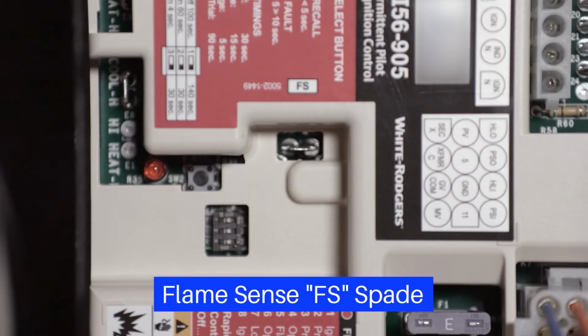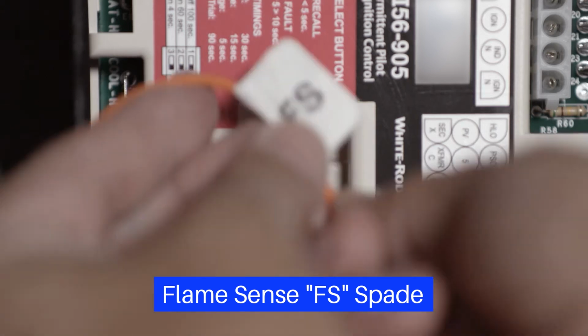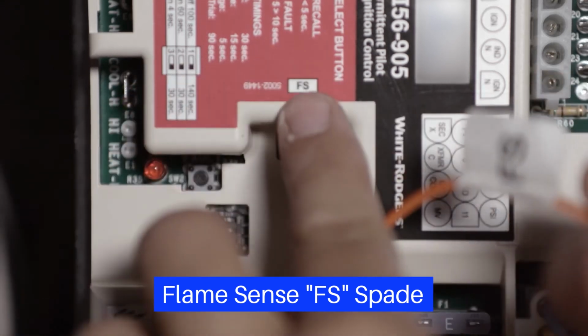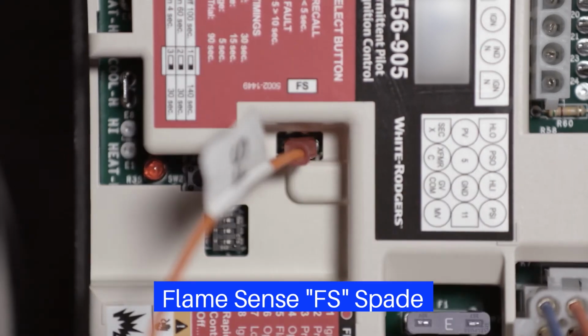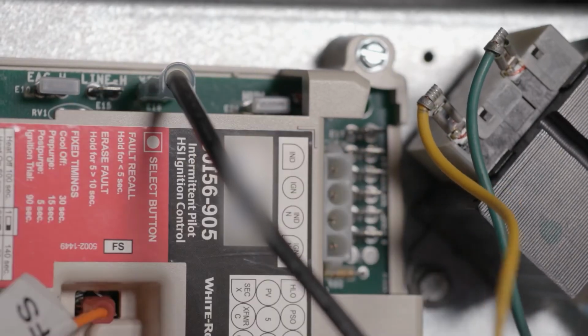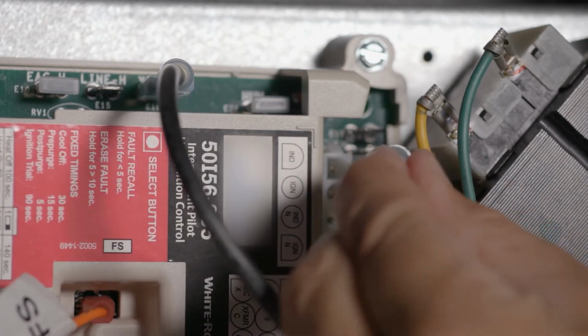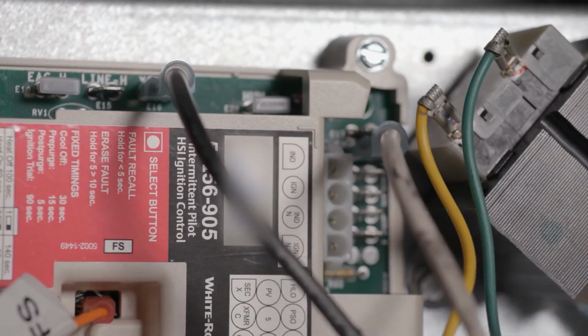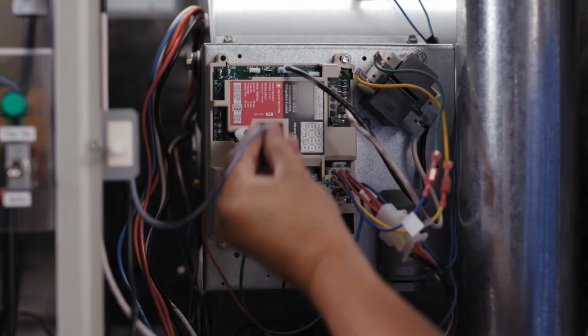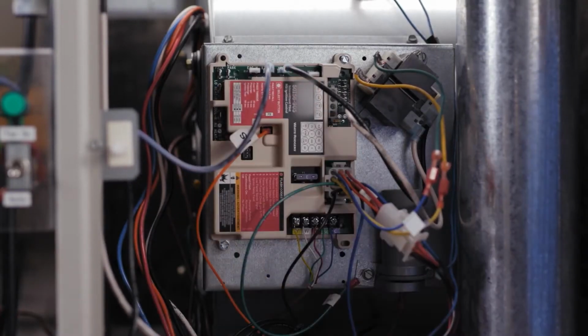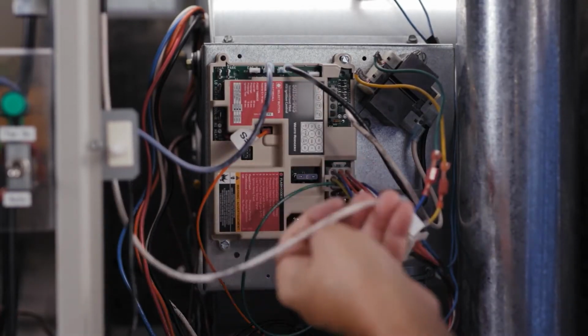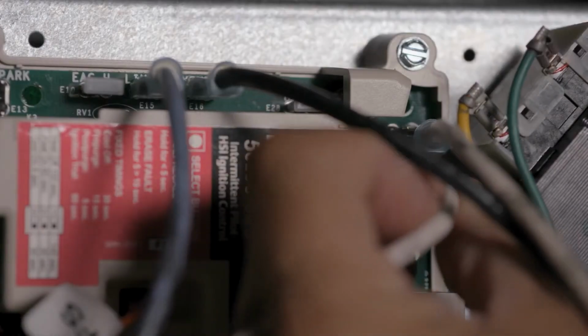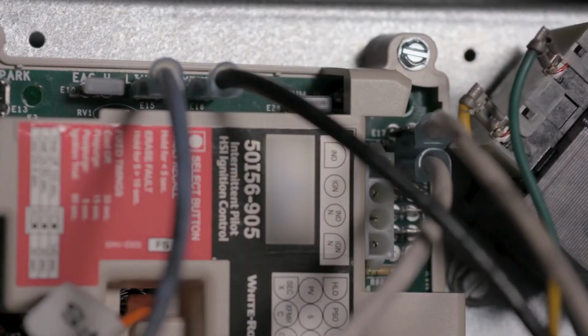Plug the orange flame sensor wire that was run from the pilot assembly extension harness onto the control board 3/16" spade labeled FS. Connect the 120-volt transformer hot to XF-MR-H. Then connect the transformer neutral to a line neutral terminal. Connect the 120-volt line voltage power to line-H. Then connect the neutral to a line neutral terminal.